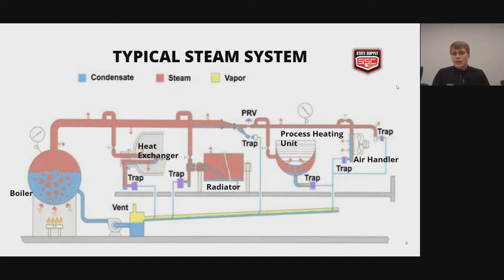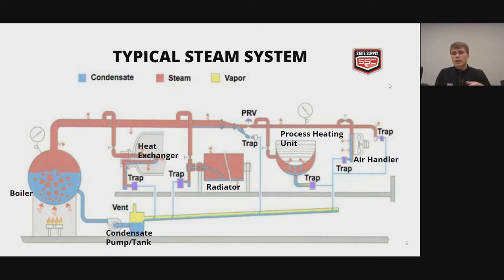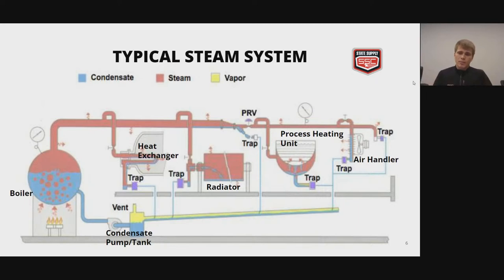Another use would be an air handler. For heating a large building, you can run steam through coils in the air handlers and then run a fan over it. At the end of the line we have a drain trap to drain any water in the line, preventing water hammer and water buildup. Once the steam goes out through the steam trap, it will go back down into the condensate pump and tank to be typically reused, unless it's contaminated.